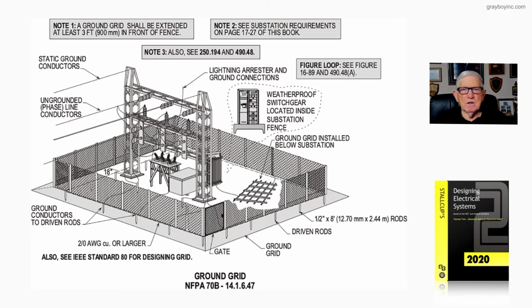And then you notice you have your ground grid installed below the substation, and from the point of the equipment that you see with that bonding jumper to the grid should read about 1 ohm if possible, in accordance with IEEE 80 that you see in bold type here, in designing your grid. And then we have the electrodes driven into the ground, and they're a 1/2 inch by 8 foot. And there are certain distances around that substation in accordance to the size of the substation as illustrated and required in IEEE 80. You can't hardly perform maintenance on a substation in accordance with NFPA 70B without having the IEEE 80, because we're referenced there.